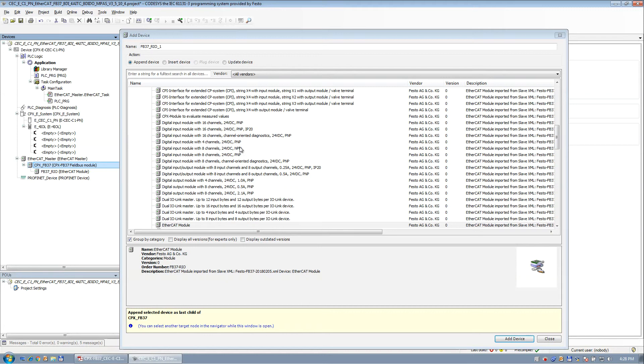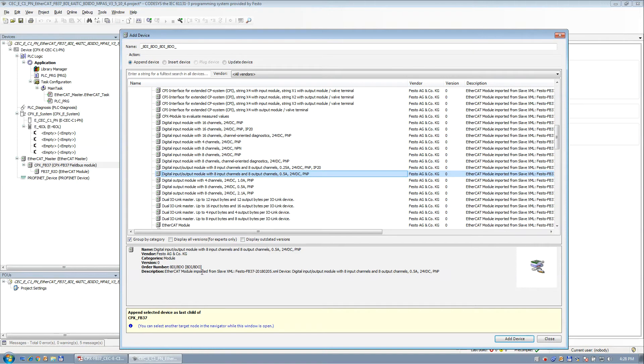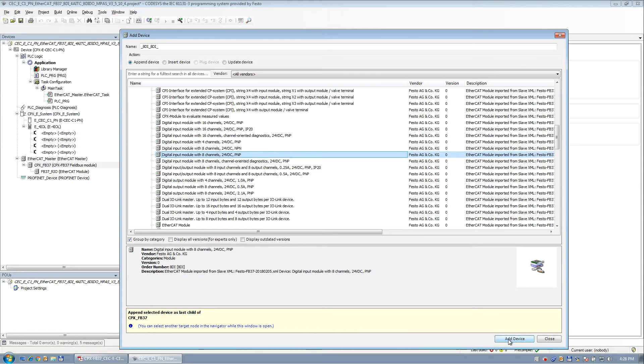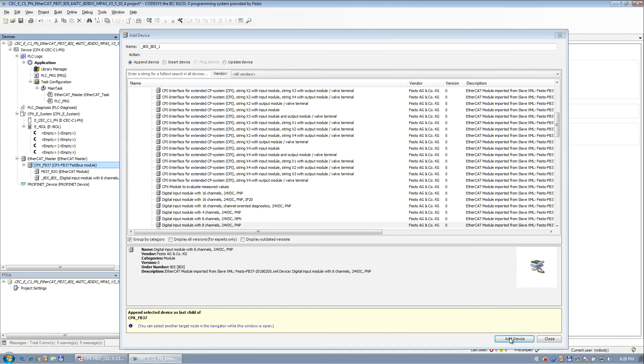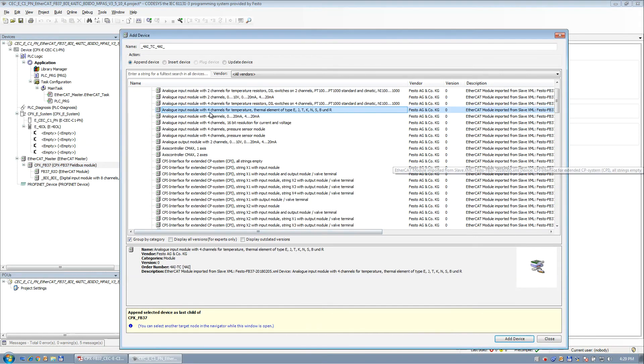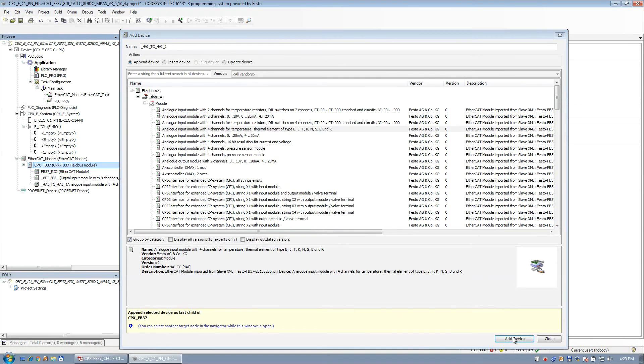So right here, we're going to add this. And then I just like to point out one thing. The description here, the name is quite, I don't know, overwhelming and descriptive. What you should be looking at down here is this right here. That's a little easier to contend with. When you look at the front of the module that I'm going to add, it'll have this lingo on it. So right now we're looking for 8DI. And there's an 8DI right there. Say add device. And then the next one would be a 4AI. So we're looking for the thermocouple. And so this right here. So that's the TC I have. So add a device.